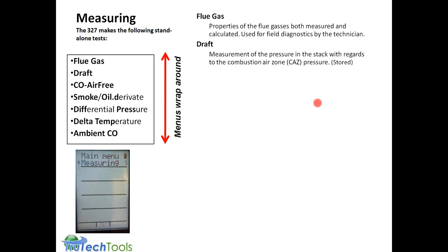The draft is a measurement of the pressure in the stack with reference to the combustion air zone pressure. It's a differential type measurement. It's a stored value that would be automatically stored after you take the test, and then it would be available in the printout.